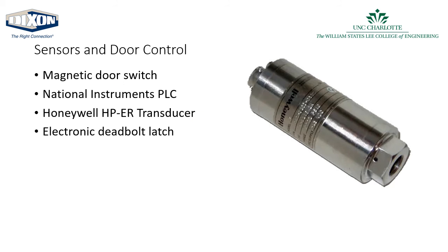On the electronic side, the system uses a magnetic switch to make sure the door is closed before it begins pressurizing. Once the high pressure transducer that records the pressure data for the tests reports that the system has begun pressurizing, the system engages the electronic latch and does not disengage it until the transducer reports that the system has fully depressurized.